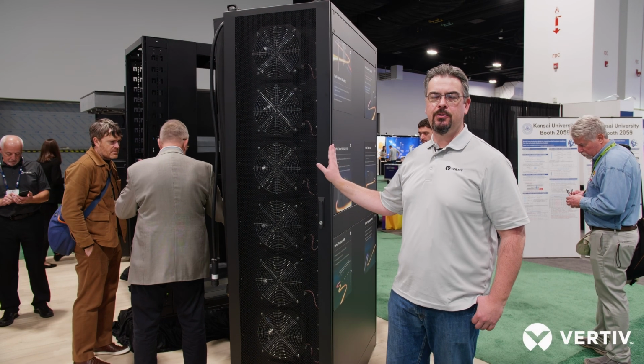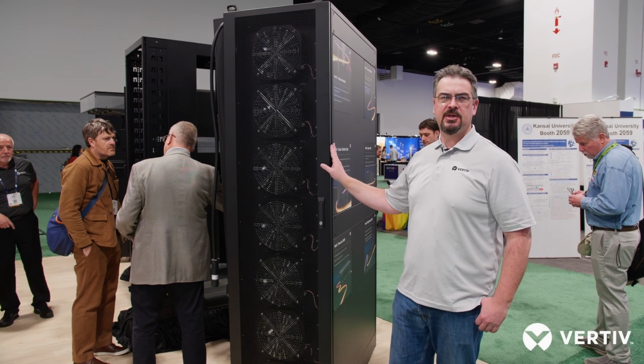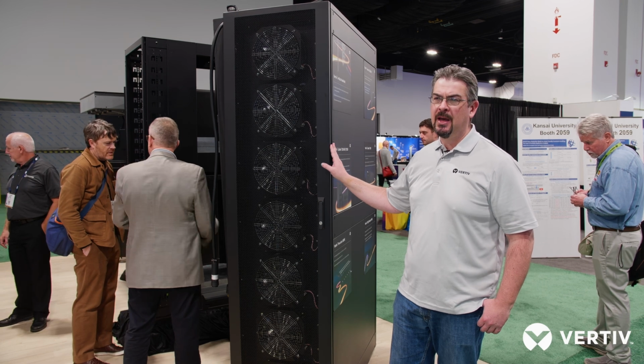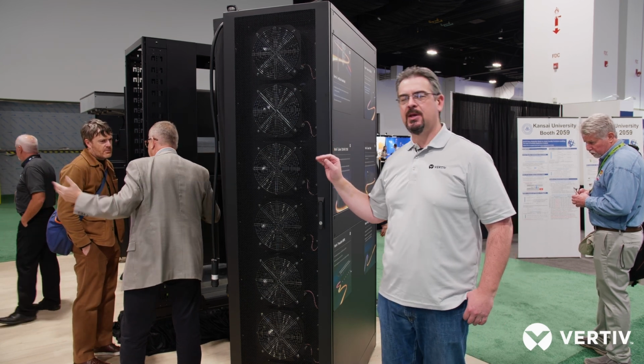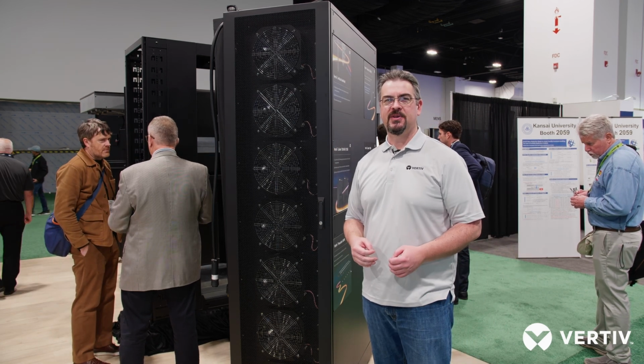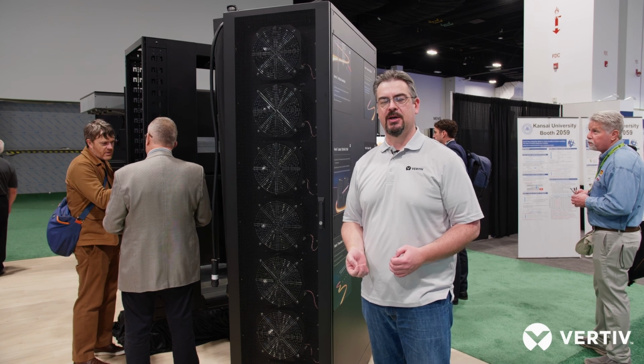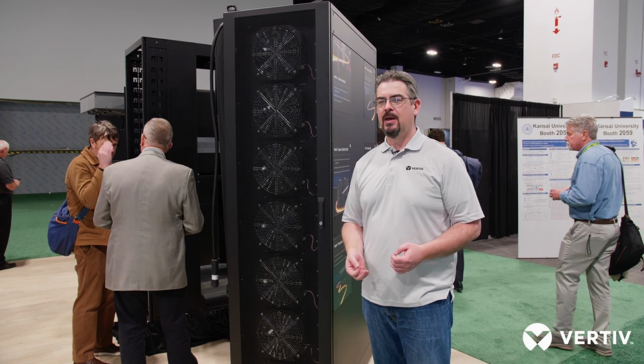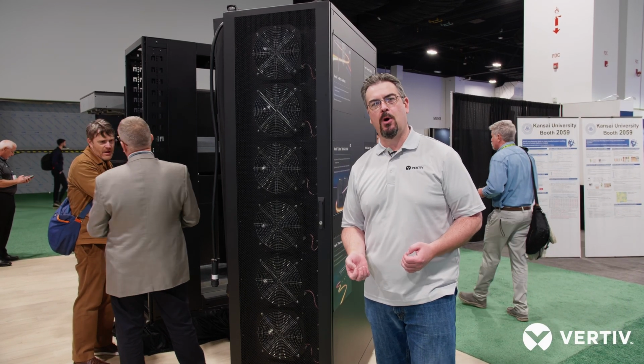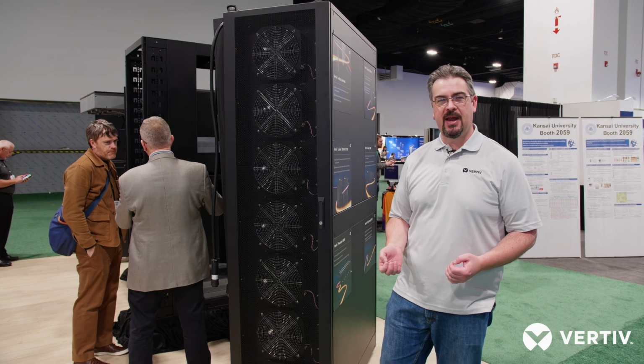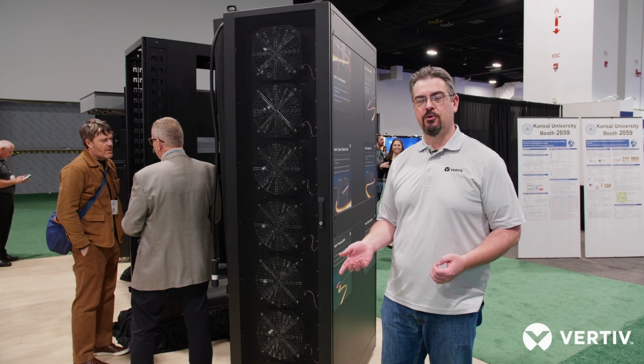Our XDU 070. This is another CDU, or coolant distribution unit, but this one is built with a different purpose. This unit is designed to go into facilities that don't have liquid cooling on site, so they don't have a chiller available and aren't able to reject that heat back to the chilled water plant. They have to rely on their existing air conditioning technology in order to remove that heat.